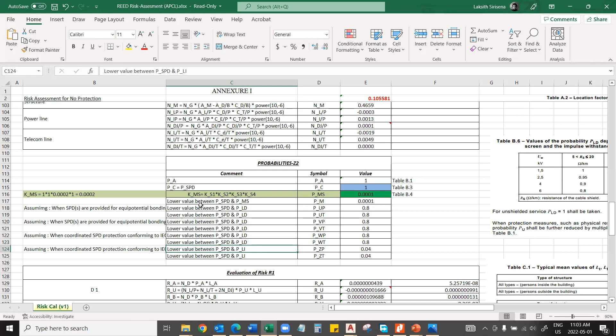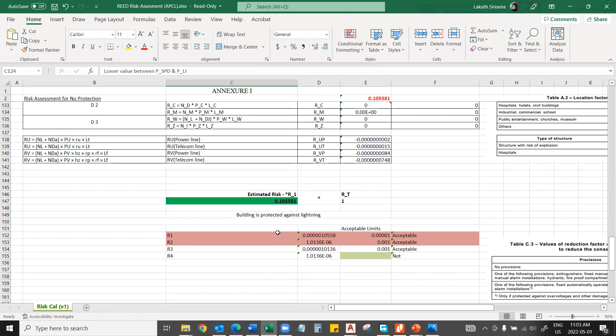Okay, so either you are going to have separate buildings, or if you have considered it as a whole. But if you are connecting it with the same earthing system and if you are bonding them, then you have a risk, associated risk with that. So that should be taken into account as well. So these are the calculations done according to the standard. So what you have to do is, if you have all rest of the things as mentioned, where you can play in this calculation is the lightning protection class. The first thing you can do is this lightning, because you cannot change number of people coming to the premise.